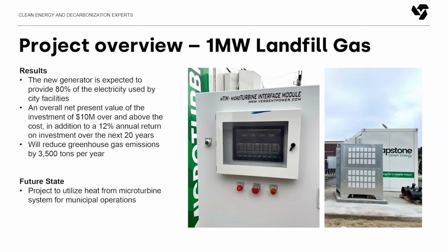On heat recovery, the last thing I'll mention is that there are multiple types of heat recovery we can do from the exhaust stream—it's not just hot water. We can incorporate an absorption chiller and do chilled water, so if there's a facility nearby that needs chilled water, we can get about 500 tons of cooling out of a single C1000. If there's a need for steam at a local facility nearby, we can produce a significant amount of steam with a heat recovery steam generator. And finally, the exhaust is clean enough that it can be common ducted into direct exhaust applications as well.